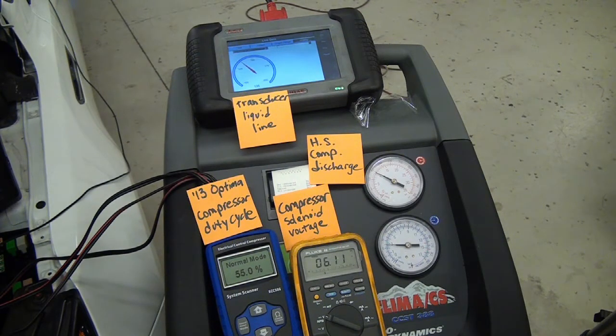Right away we can see the high pressure side going up. At the compressor discharge we're climbing up pretty close to 150 now. And on the liquid line we've gone up to about 140. And they're both still climbing. The low side seems to be staying steady, although it looks like it might have dropped just a little bit.